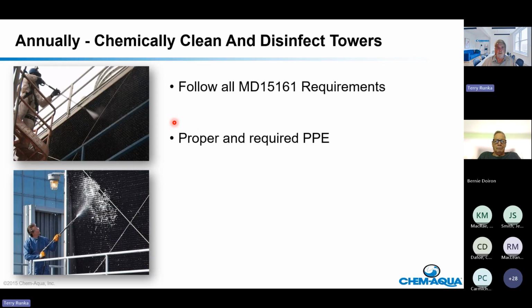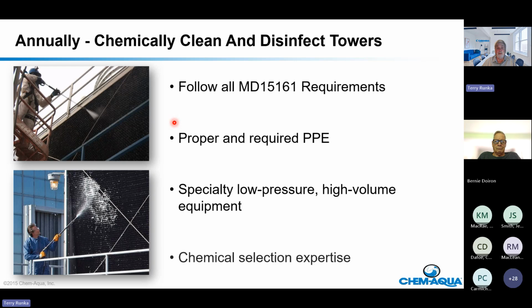That leads us to the easy part. Every one of your programs says Chem Aqua Services, a division of Chem Aqua, will come in at least once a year, some places twice, to clean and disinfect your cooling towers. They're dirty, stuff sticks to them, and water trades over them. The sumps are only the bottom, but the rest of the cooling tower gets dirty too as the water flushes over it. All the standards say physically cleaning your cooling towers at least once a year helps minimize Legionella, keeps towers cleaner, and saves water. There are all kinds of advantages to it, and that's part of all your programs.